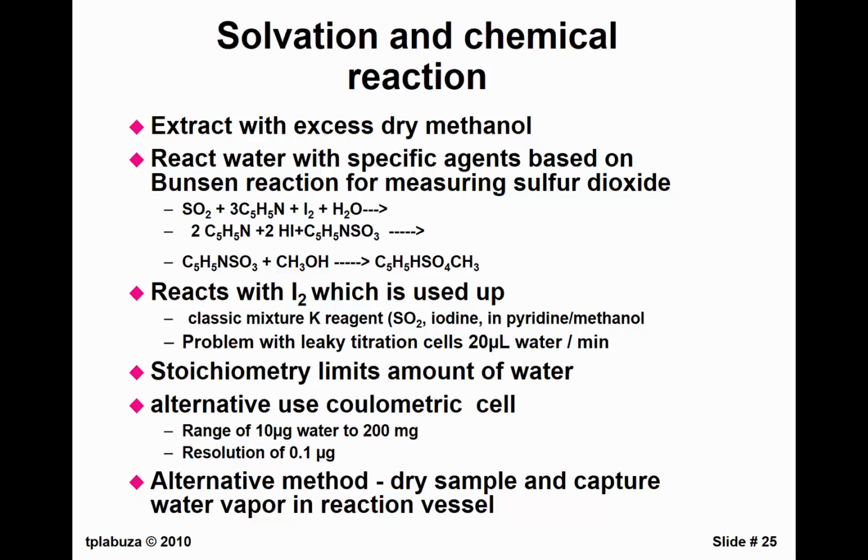Now, the Karl Fischer you have gets rid of most of this because it uses a coulometric method to produce the iodine. And it just produces enough iodine to react at the same level with the amount of water that's in the system. So it's a very simple electronic system that does this.